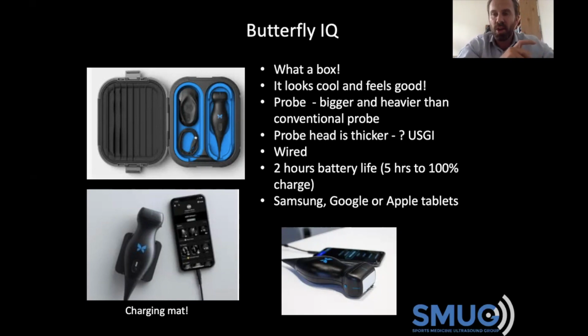And it doesn't take too long to get used to using the probe. But you do need to remember that this probe is bigger and it is heavier than your conventional ultrasound probe. So it does take a little bit of getting used to. Now, one of the reasons it's bigger is because obviously it's 3 probes in one, but also the second reason, and one of the reasons it's heavier, is actually the battery is within the probe. So although it's wired, it's not wireless like the Clarius, it is a wired handheld machine. The battery is actually inside it.